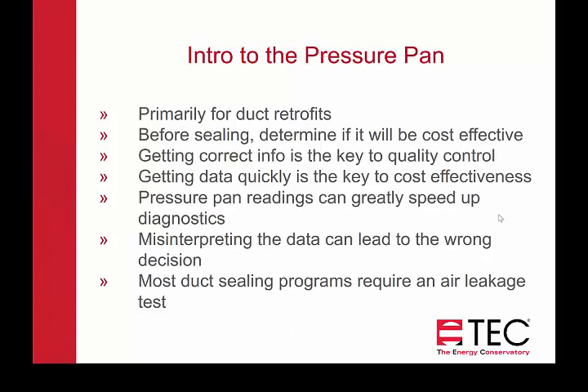Most duct sealing programs offering incentives and rebates do require an air leakage test, so you'd still need to do a duct blaster test. The pressure pan is primarily used in most cases to diagnose where the leaks are — it doesn't take the place of duct blaster tests. Although there are some programs that have used pressure pan readings alone and not an air leakage test.